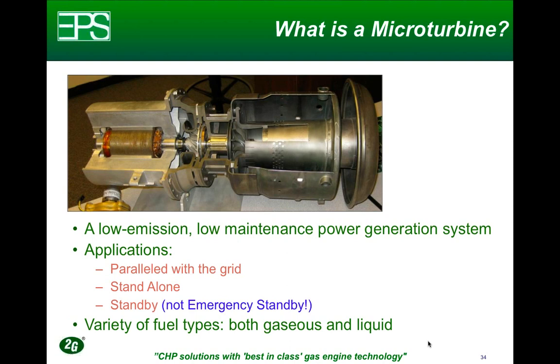So when looking at microturbines, if emergency standby as defined by CSA 282 is required, then microturbines cannot be utilized because they are not recognized by CSA 282 to meet its criteria. And the main reason is that it will take some time for the microturbine to start up, where CSA 282 does require that a unit is ready to accept load within 15 seconds from a power outage.